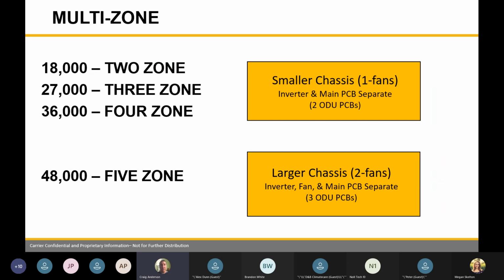So when we get into the multi-zone units, they're a little bit different as well. We have 2 zones, 3 zones, 4 zones, plus we have 5 zones. So the smaller chassis, the 2 to 4 zones, you're going to be looking at an inverter board and a main board. When we get up into the big dog, now we're more zones, we're more stuff going on. We're going to have inverter boards and we're going to have main PCB boards separate as well. So that unit there is going to have 3 boards now. So just be mindful of that. If you're working on a big unit and you're not figuring out the problem, there might be another board in there that you need to look at.